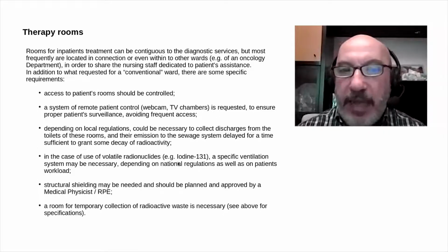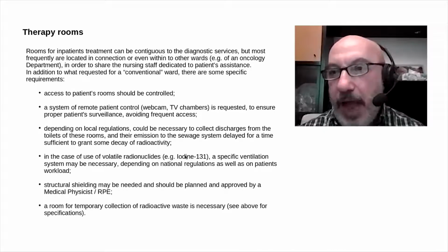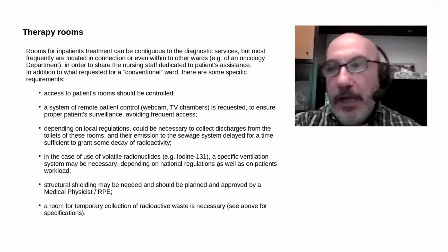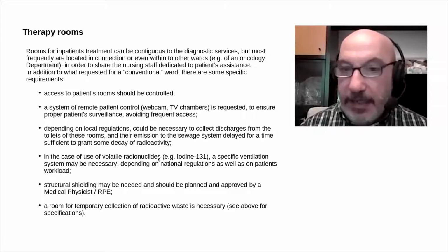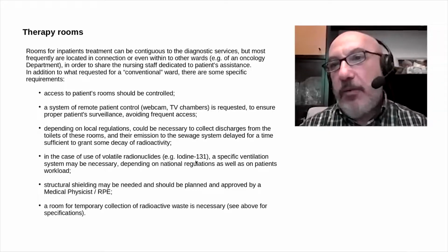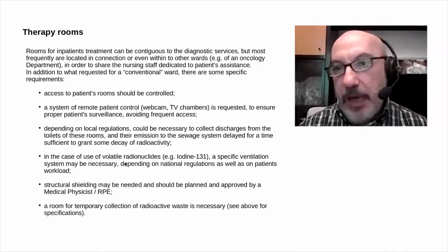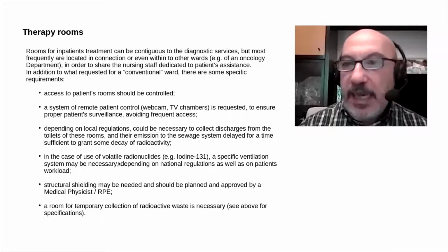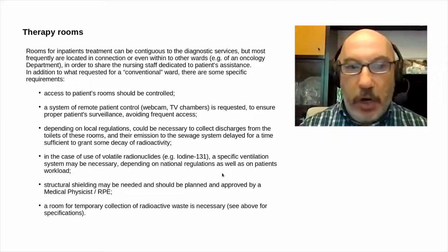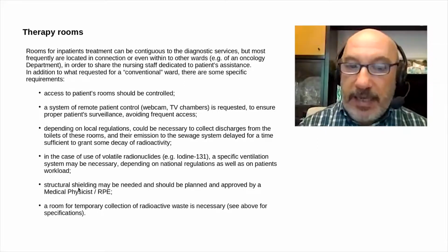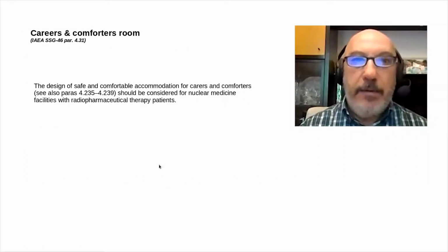In the case of volatile radionuclides, and this is the frequent case of iodine-131, the most important therapy radionuclide, there should be a specific ventilation, since the patient releases some iodine-131 with their breath, and so there can be a contamination of the air. It is necessary to have a good air extraction fitted with appropriate filtering, like charcoal filtering. Structural shielding, once again, should be approved by a medical physicist or radiation protection expert, and I will come back to discuss the example of all these points even later.